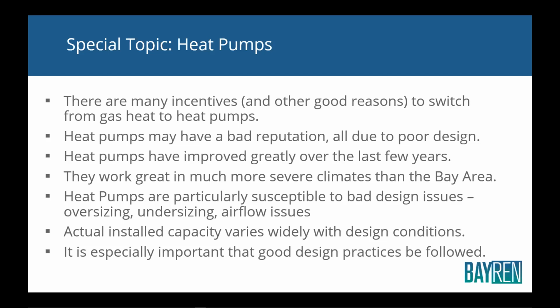So heat pumps do have a bad reputation. You know, people say, oh, they blow cold air. Oh, they run on electric resistance strip all the time. They don't work in really cold weather. Those are not the problem of the equipment. Those are the problem of the person who designed the system. The installer who put those heat pumps in is to blame for the problems that these people are having.